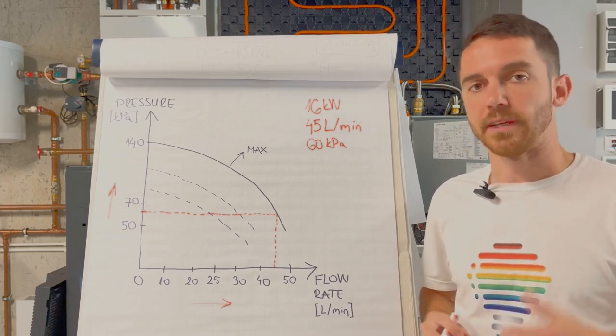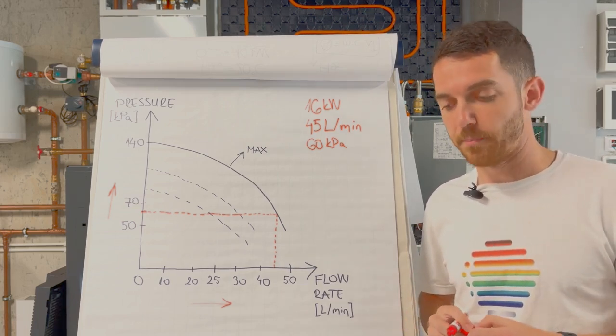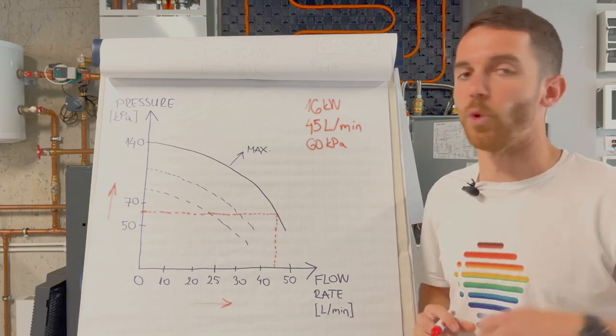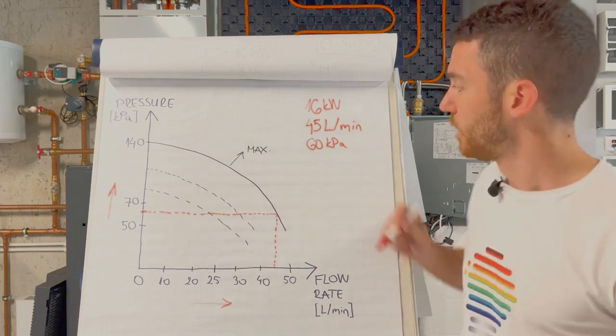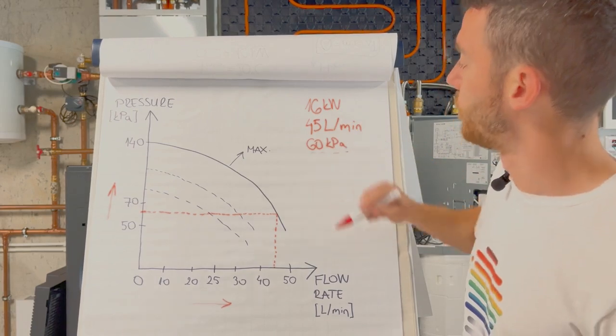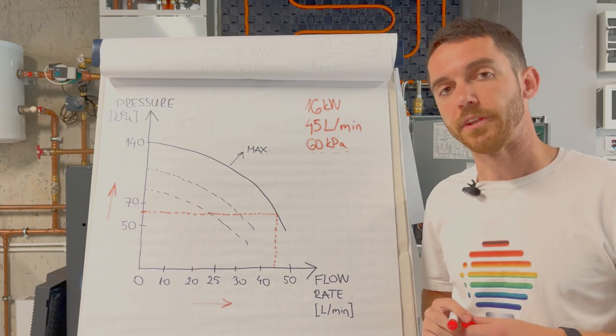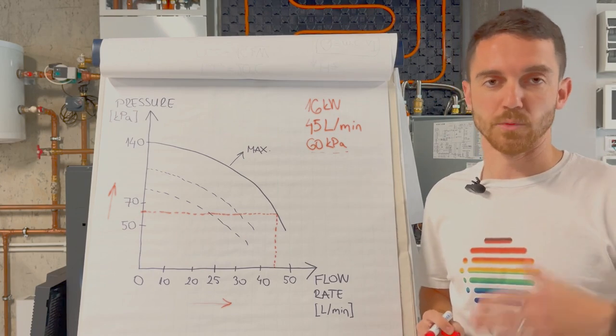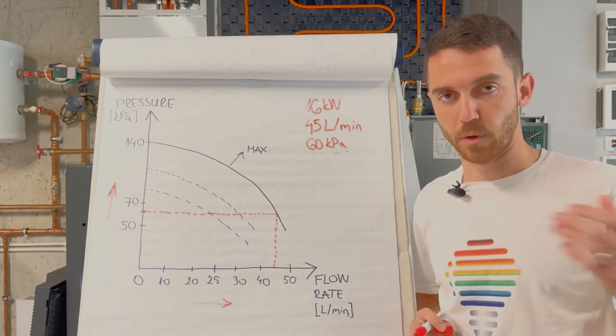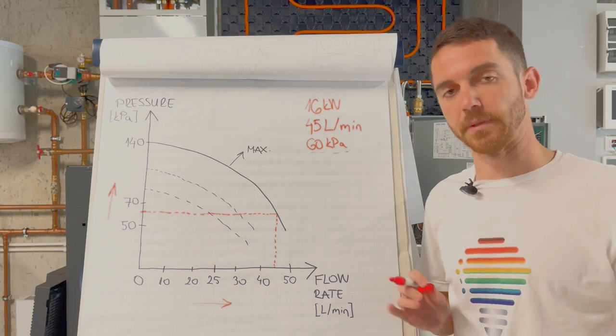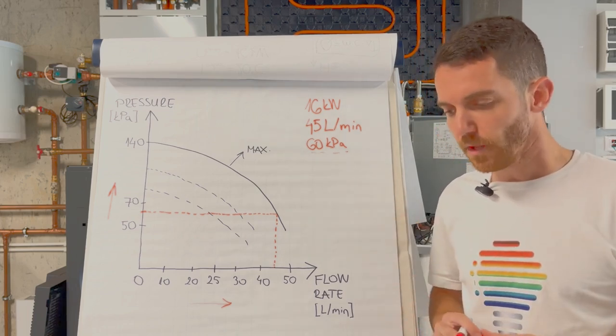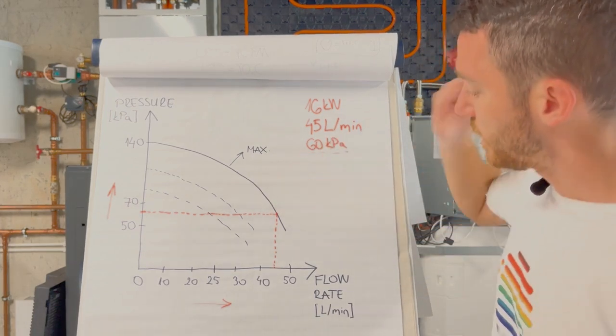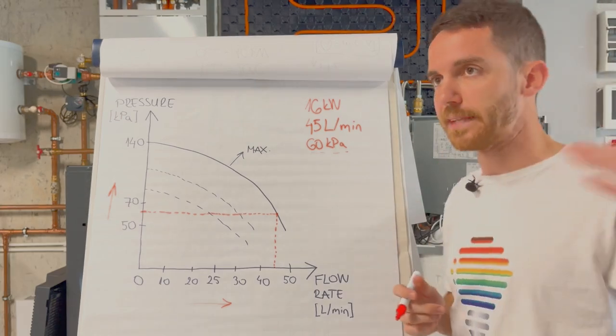I showed you in previous videos, normal underfloor heating installation with good design primary pipe, it's not more than 30 kilopascal, 40 probably on the top. But 60 you will probably not have in your installation. For radiators it's the same, only if it's really old with microbore, with 8 millimeters and 10 millimeters pipes. But let's focus on more than 90 percent of installation.